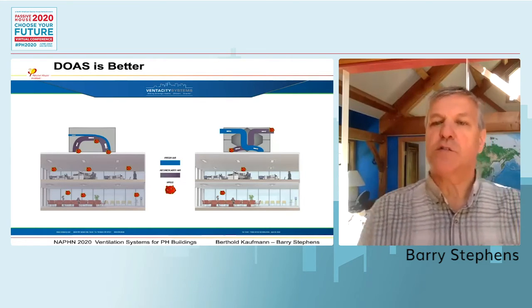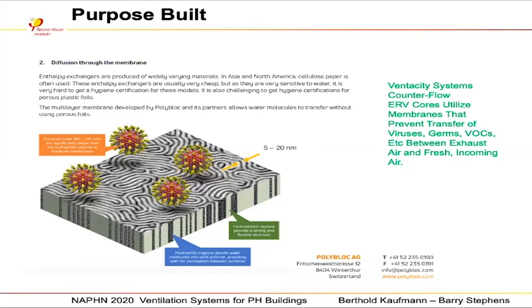Another thing is if you are using counterflow heat exchangers with membranes, these membranes are a lot like Gore-Tex, where they allow transfer of water vapor molecules, which are very, very small. And as shown here, very tiny water vapor molecules will pass through that membrane, but viruses, VOCs such as formaldehyde, and other pollutants, even smells, do not pass through from one airstream to the other. So having, in effect, a certified ERV with cores made with membranes that are certified, basically, that do not allow passage of viruses, germs, VOCs, and so forth, is critical.